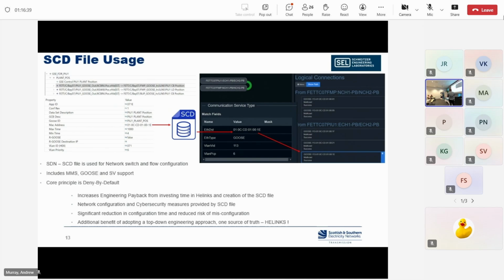You get the full benefits from configuring your IEDs, your Goose and your SVs. But if you take it further and use the SCD file for other things, this method allows you to fully configure a deny-by-default network using only the rules available within the SCD file. In this case, you can see this message taken from Helinks.